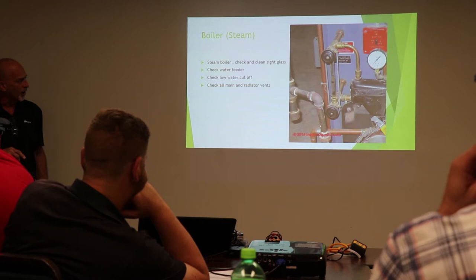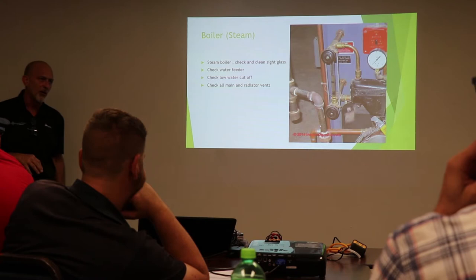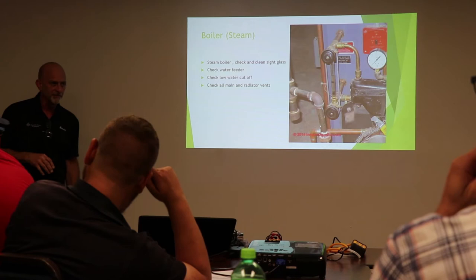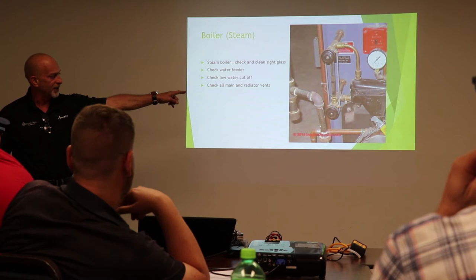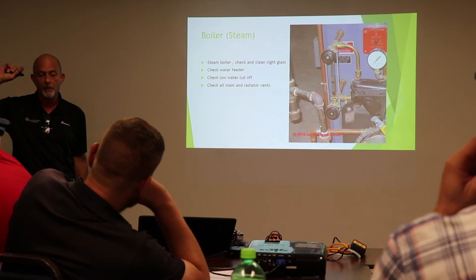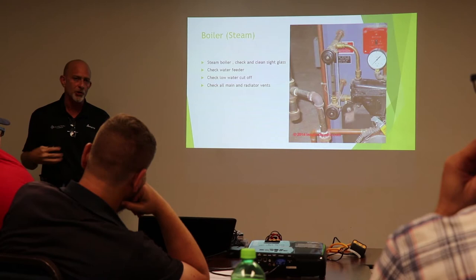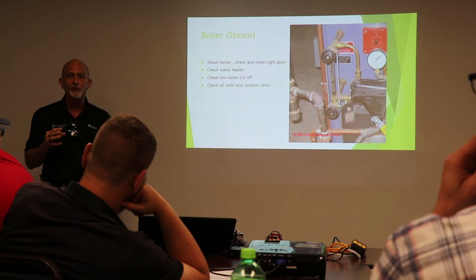Years ago, everybody told homeowners, you need to skim off your boiler at least once a week. Skim off on a steam boiler means take your valve, open it till the boiler shuts off, or some people drain them all away. By doing that, you're adding extra oxygen into that, and steam boilers don't like it. You will greatly reduce the life of a steam boiler by doing that.